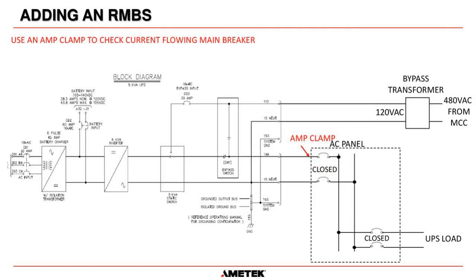So before we even start installing a remote manual bypass switch, we need to know how much current is flowing from the UPS into the AC panel. Okay. So let's say this is a, well, it says it's a 5 kVA system. So a 5 kVA system, it's usually going to be about 40 amps is the expectation, full load current. But we all know that no UPS is loaded to its full capacity usually. So let's say there is 20 amps measured with our amp clamp.